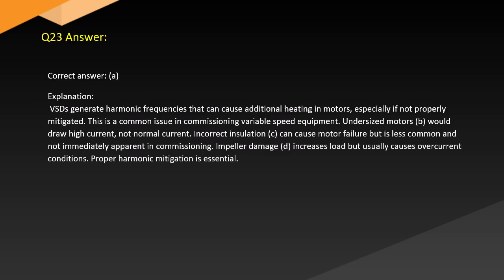Answer. Correct answer. A. Explanation. VSDs generate harmonic frequencies that can cause additional heating in motors, especially if not properly mitigated. This is a common issue in commissioning variable speed equipment. Undersized motors, B, would draw high current, not normal current. Incorrect insulation, C, can cause motor failure but is less common and not immediately apparent in commissioning. Impeller damage, D, increases load but usually causes overcurrent conditions. Proper harmonic mitigation is essential.